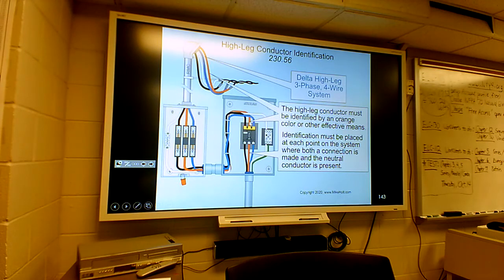Another thing is when you have power like that feeding a breaker panel, there has to be a sticker inside saying that there's a high leg in there, and you have to identify which one, and that you're not allowed to use that high leg for single phase loads. If you do, you're going to burn something up. And they say it's happened before, people, and I wouldn't doubt it.